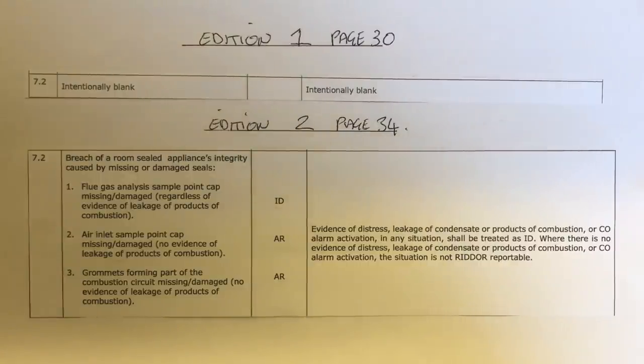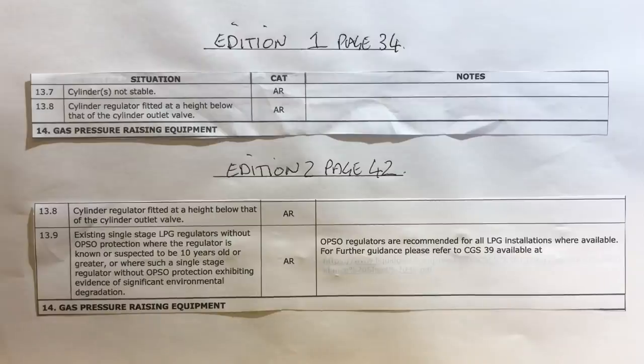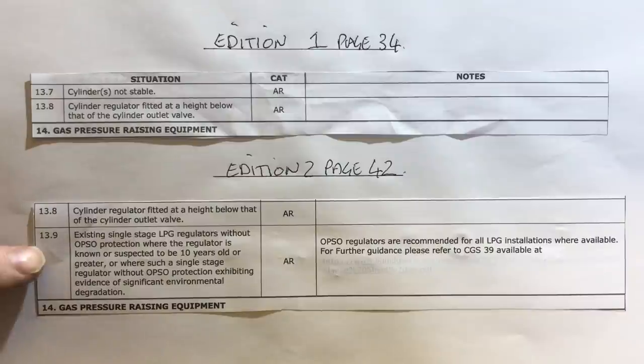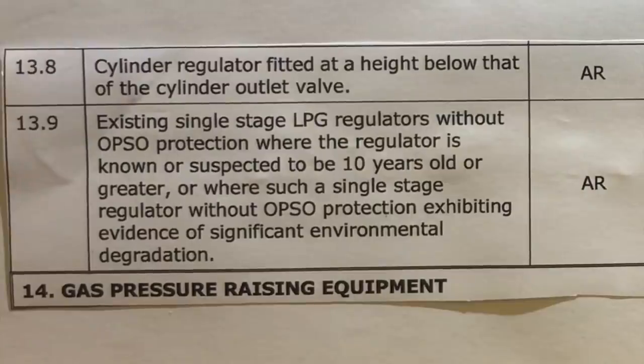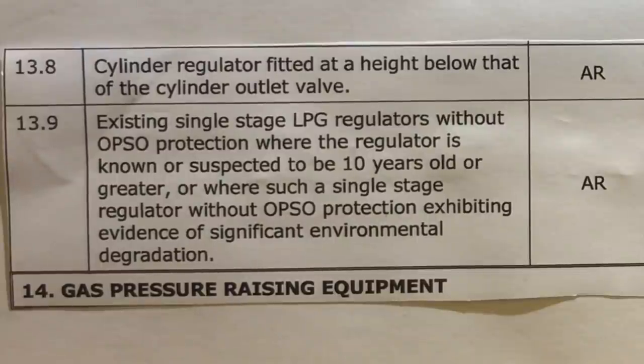The last change is table reference 13.9, which did not exist in edition one and has been added to edition two for LPG. This situation provides guidance where existing single-stage LPG regulators are without over-pressure shut-off protection, where the regulator is known or suspected to be 10 years old or greater, or where such a single-stage regulator without over-pressure shut-off protection exhibits evidence of significant environmental degradation.